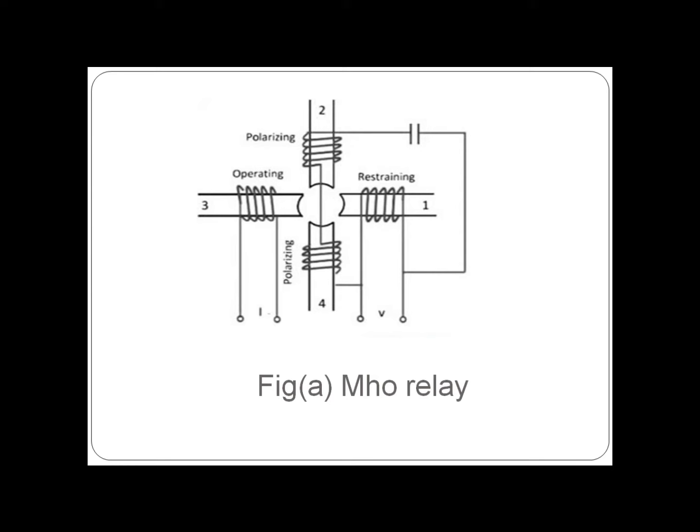The restraining torque produced is proportional to the square of the voltage, V², in Mho relay, while the operating torque is proportional to the product of voltage and current, VI.